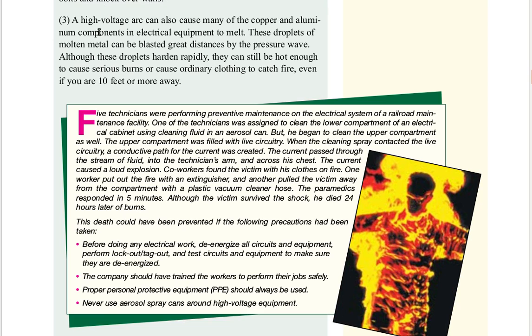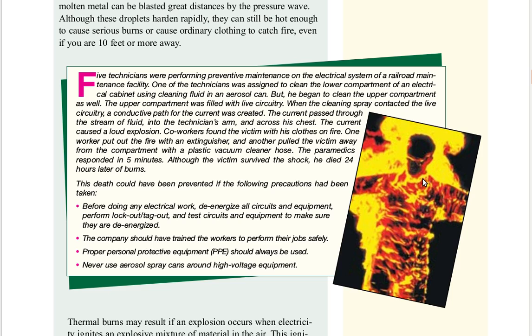Three: the third hazard. A high voltage arc can also cause many of the copper and aluminum components in electrical equipment to melt. These droplets of molten metal can be blasted great distances by the pressure wave. Although these droplets harden rapidly, they can still be hot enough to cause serious burns or cause ordinary clothing to catch fire, even if you are 10 feet away. You see in this picture, someone's clothing has caught fire.